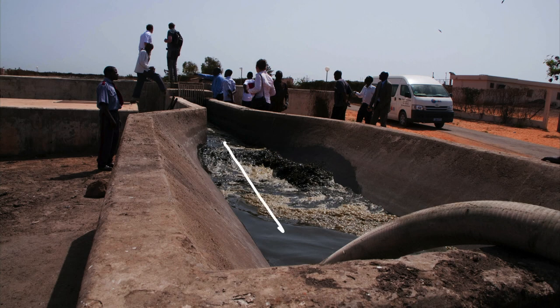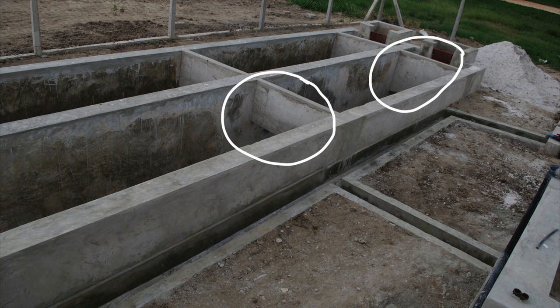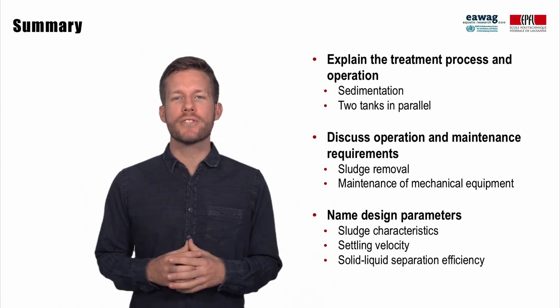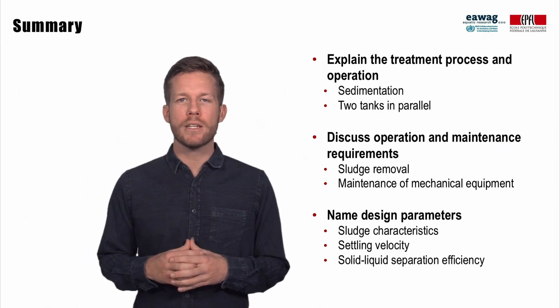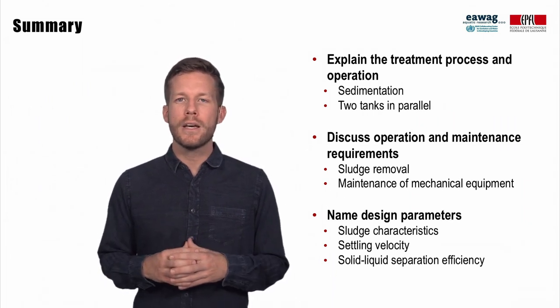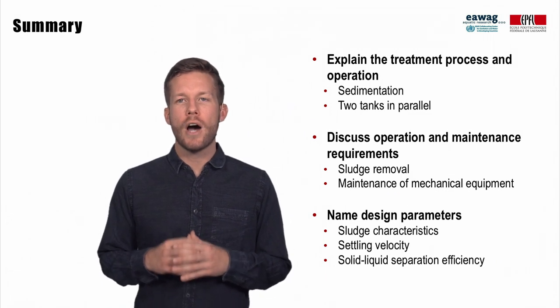A discharge area for sludge before a settling thickening tank can be a good way of mitigating turbulence. In addition, baffles at the inflow and outflow of settling thickening tanks can help reduce turbulence and ensure good solid-liquid separation efficiencies. In this module, we learned that the treatment process and operation of settling thickening tanks is based on sedimentation. Frequent removal of sludge is important so the tank operates as designed, requiring maintenance of mechanical equipment such as pumps and front loaders. Design parameters specific to settling thickening tanks are related to sludge properties and include the settling velocity and the solid-liquid separation efficiency.